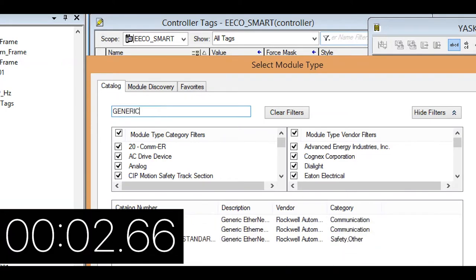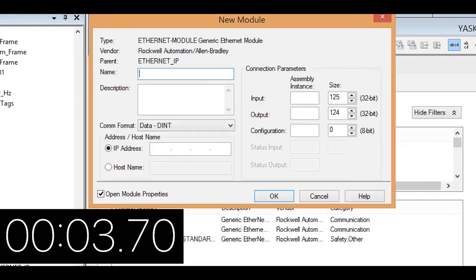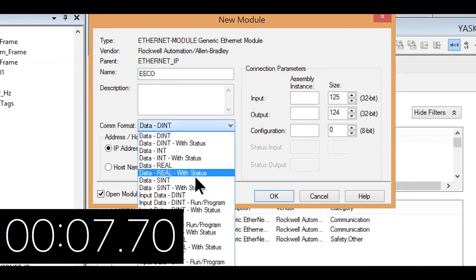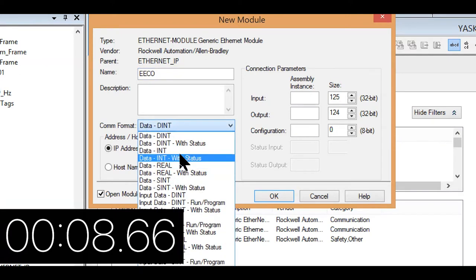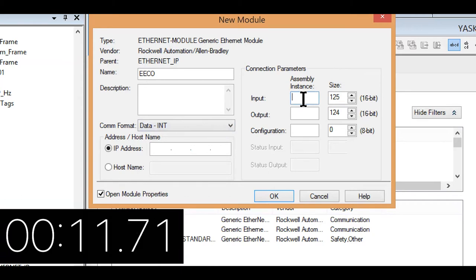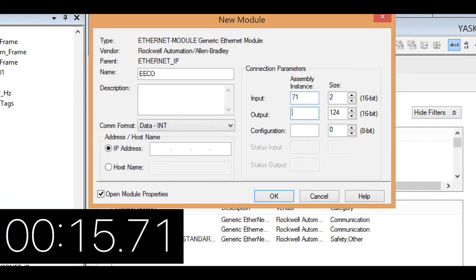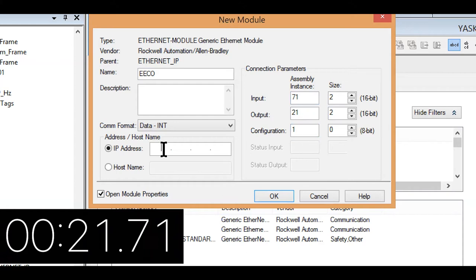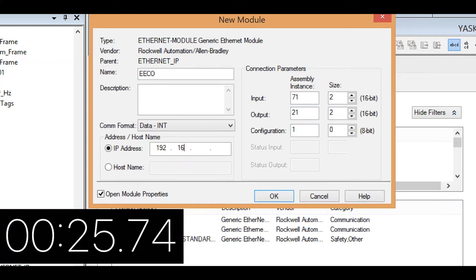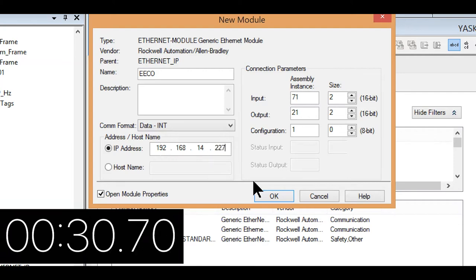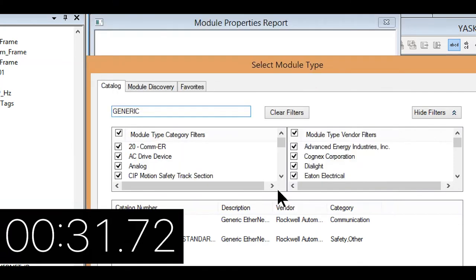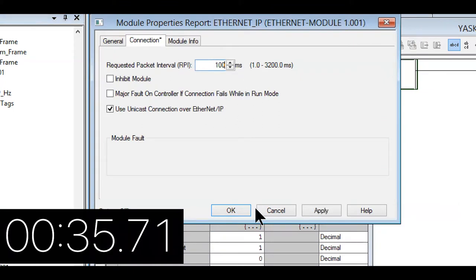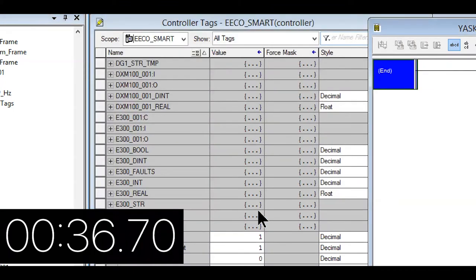So we're going to go to a generic Ethernet module. We'll call it EECO. The Comm format. We'll change that to data INT. The input. We're going to do 71.2. Then we'll go to 21.2. We'll go to 1. The IP address. 192.168.14.227. Okay. We're going to change this to 100 milliseconds. And we're okay. And boom.